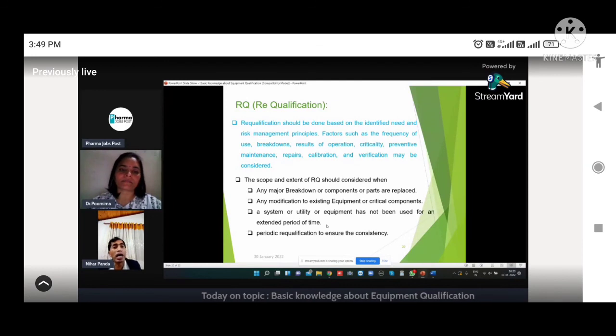Then last is RQ, requalification. Requalification means after the completion of the qualification, requalification may be required based upon the scenario and feasibility. What are the things? Like any breakdown, any major breakdown, or components or parts to be replaced or modified. Then in that condition, requalification is required. Or any modification to the existing equipment for the critical components. If any critical components need to be modified, then in that scenario, requalification is also mandatory. Or a system or utility or equipment has not been used for a long period, then also requalification is to be done. Or any periodic requalification.